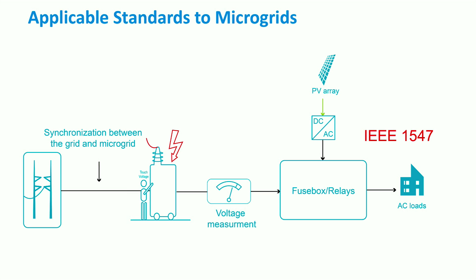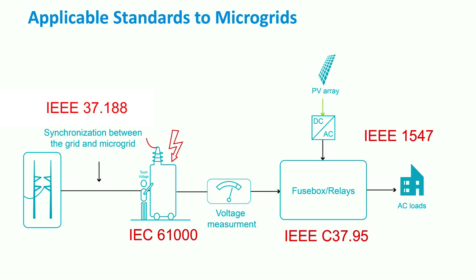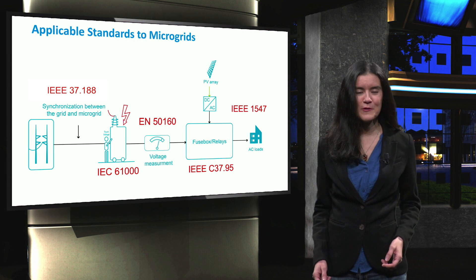IEEE 1547 provides criteria and requirements for interconnection between distributed energy resources and the main grid. IEEE C37.95 describes the protective relaying of utility consumer interconnections. IEC 61000 covers general conditions and rules necessary for achieving safety function and integrity requirements related to electromagnetic compatibility. IEEE 37.188 is the IEEE standard for synchrophasors in power systems. Finally, EN50160 describes the voltage characteristics of the electricity supplied by public distribution networks.